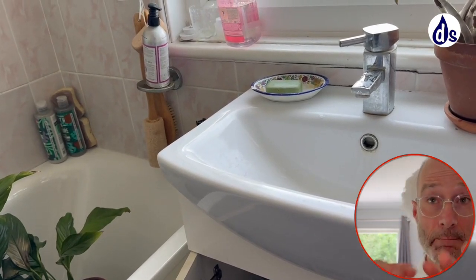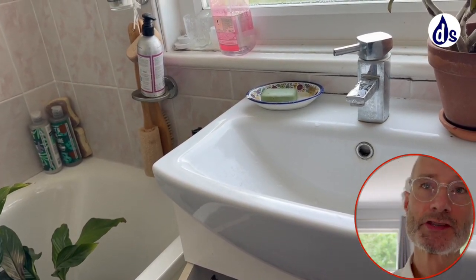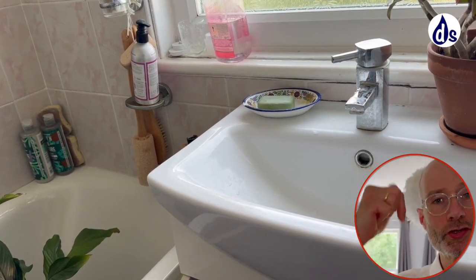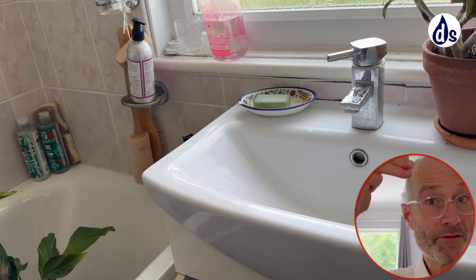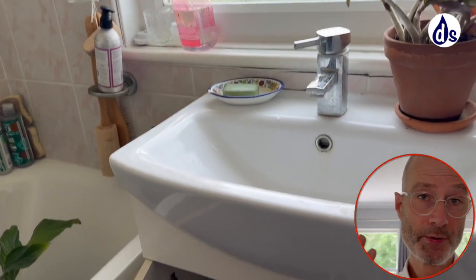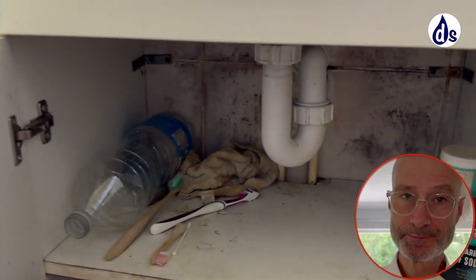You're getting mould under the sink, and mould is caused by excess vapour. It's where the surface relative humidity goes above 85% for long periods of time. So excess vapour is the primary cause, and that's defined as where the internal dew point goes above the outside temperature. You can improve it by improving air circulation, by insulation, but ultimately you don't have a fan in the bathroom, and that would be a starting point.